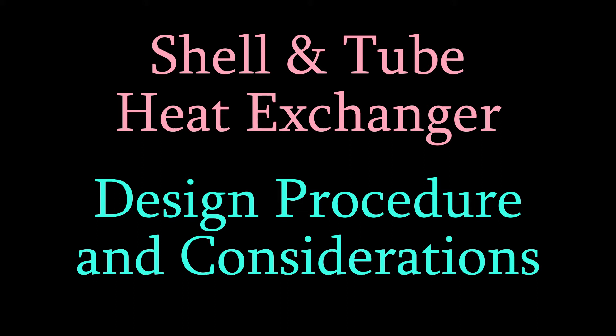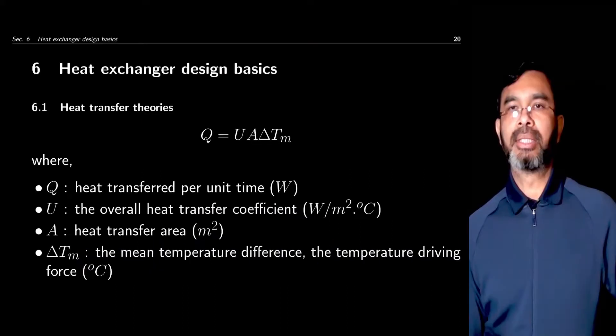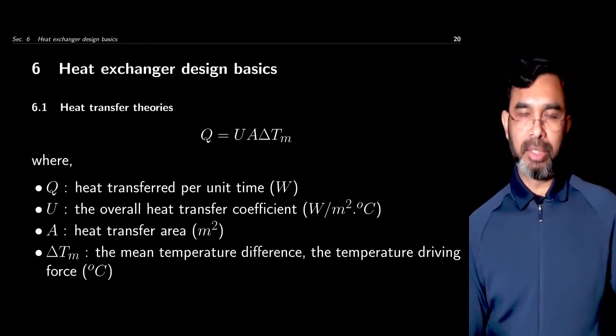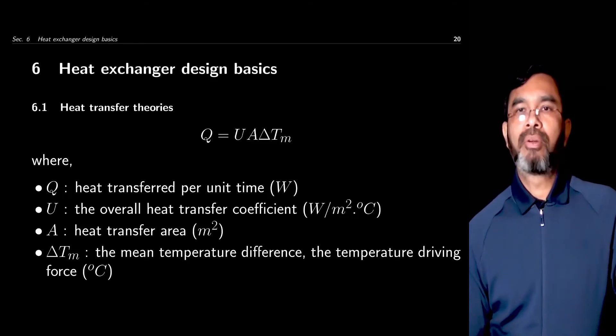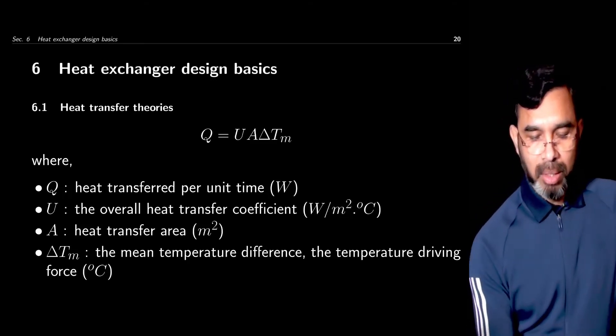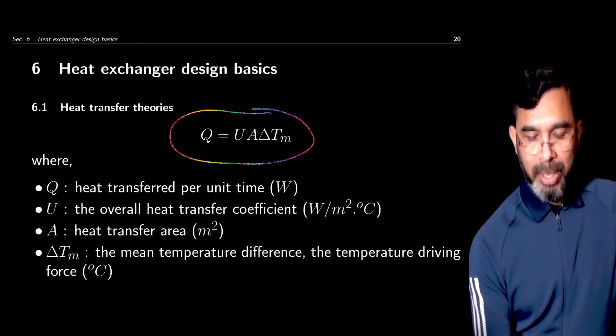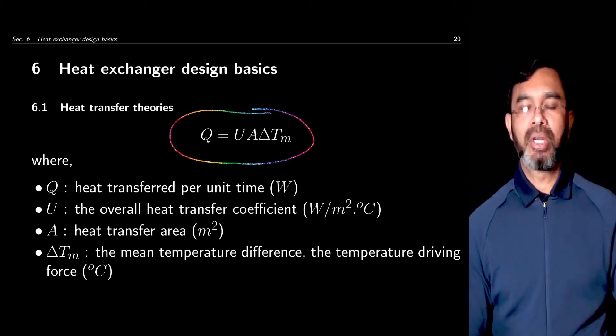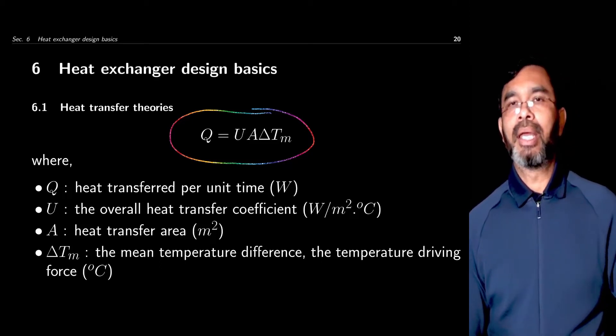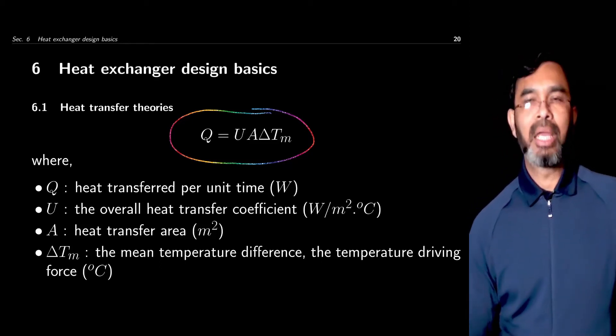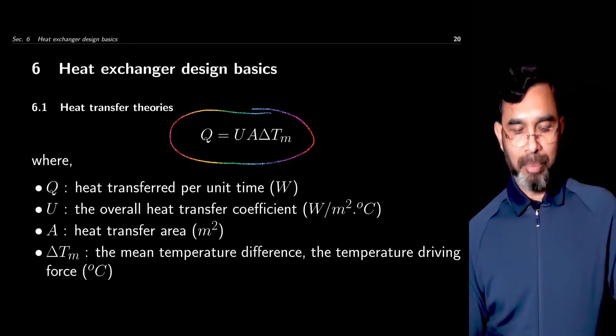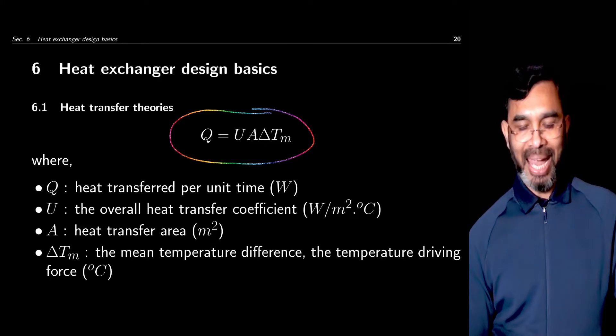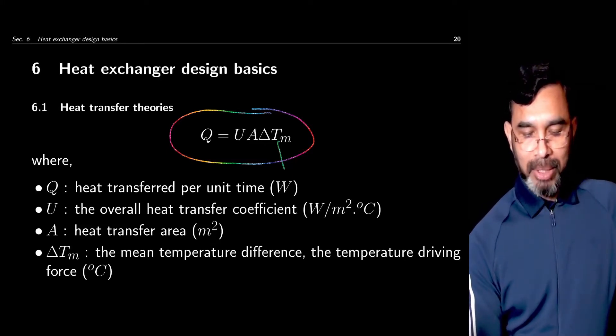In this session, we talk about some design aspects of heat exchangers, focusing mainly on the Shell and Tube heat exchanger. For all heat exchanger design, the basics of heat transfer remain the same. The main equation, Q equals U A delta T, is always applicable. Here Q is the heat transfer between the two fluids, U is the overall heat transfer coefficient, A is the heat transfer area, and delta T is the temperature difference.